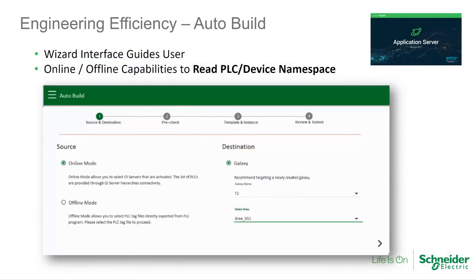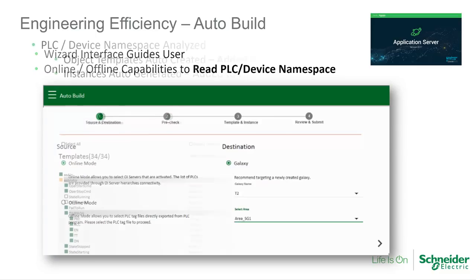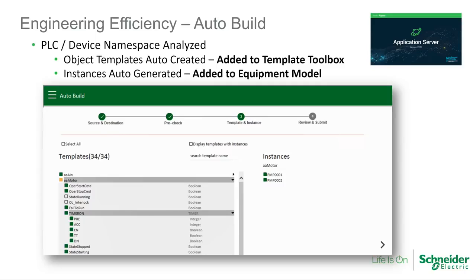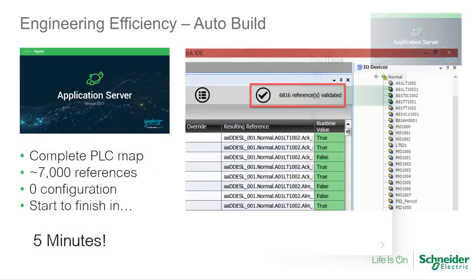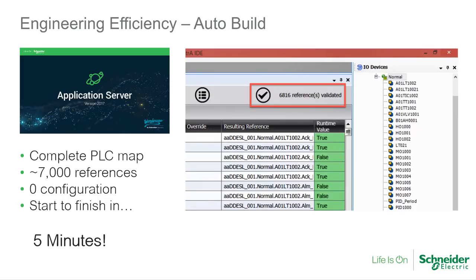Select OI servers have been enhanced to allow users to leverage the configuration that already exists in their intelligent PLCs and other field devices. Through a powerful wizard interface, users are guided through the quick and simple process of reading the namespace from their devices, which the system then uses to build object templates that model the equipment the PLC controls, and then automatically creates instances for each piece of equipment. This dramatically reduces the engineering time required and eliminates data entry errors.